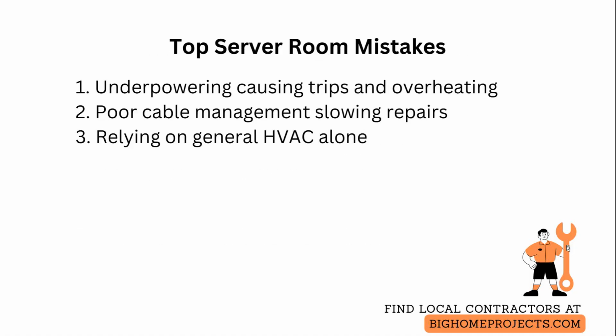Common mistakes start with underpowering the space, which causes breaker trips and overheating. Fix this by planning dedicated circuits now and labeling each circuit for the rack equipment. Another frequent issue is poor cable management that makes moves and repairs slow and error-prone. Avoid this by using patch panels, color-coded cables, and Velcro routing with documented maps.